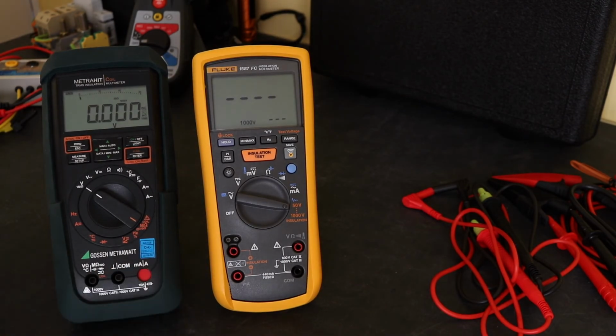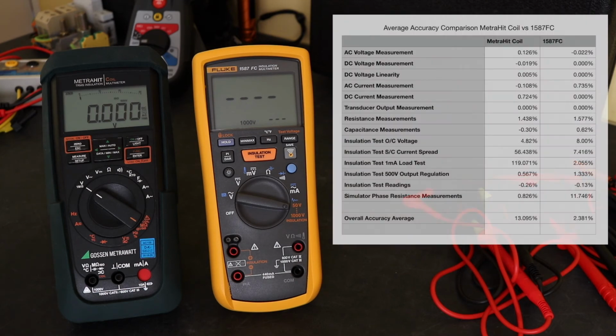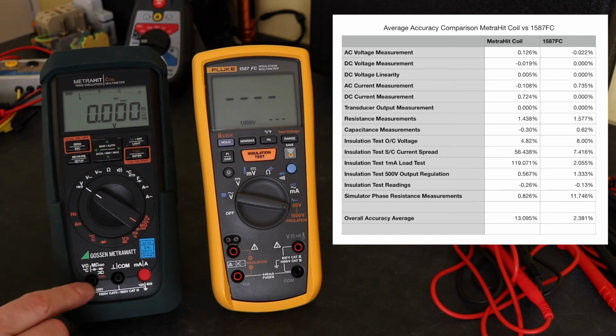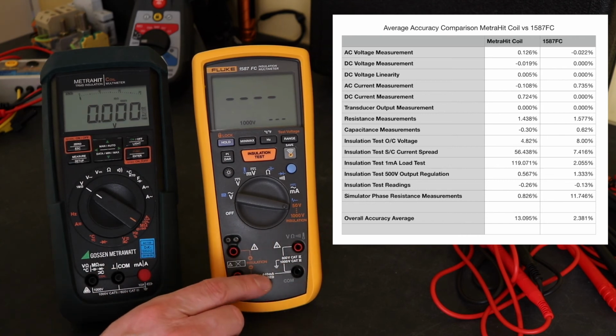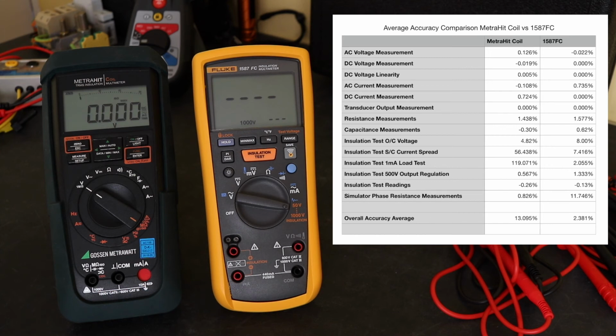Okay, I'll shove the instruments over to the left there, and hopefully I can get the table of accuracy test results up on the right hand side, and we can work our way through them. Not much of a difference really on the voltage readings, AC and DC linearity, fairly consistent between the two instruments. So measuring AC current, quite a bit better accuracy on AC current with the MetraHit coil. That's actually measuring 0 to 10 amps direct on this input, and 0 to 10 amps through a clamp adapter on the Fluke. If you flip it over to DC, you actually get a better response from the 1587 than you do the MetraHit there. That said, with the real world application of a transducer output test, both instruments were spot on. Nothing to choose between them.